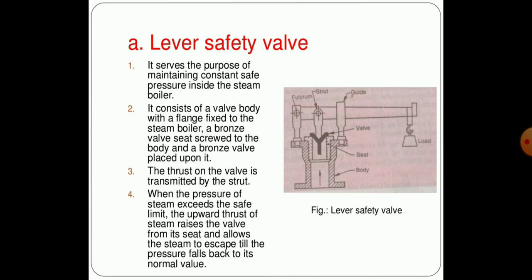It consists of a valve body with a flange fixed to the steam boiler and a bronze valve seat screwed to the body which is placed upon it. The thrust of the valve is transmitted by the strut and lever. When the pressure of the steam exceeds the safe limit, the upward thrust of the steam raises the valve from its seat and allows the steam to escape till the pressure falls back to its normal value.